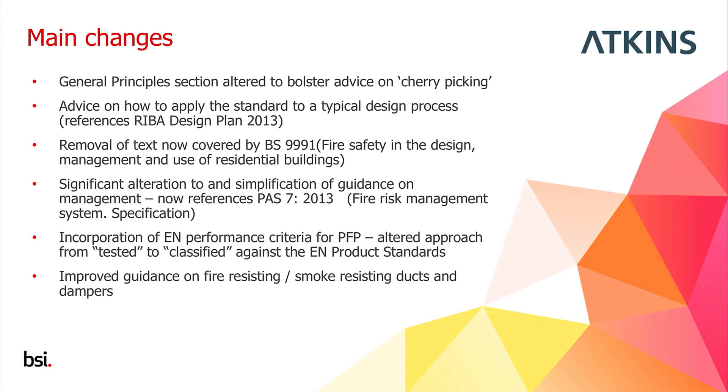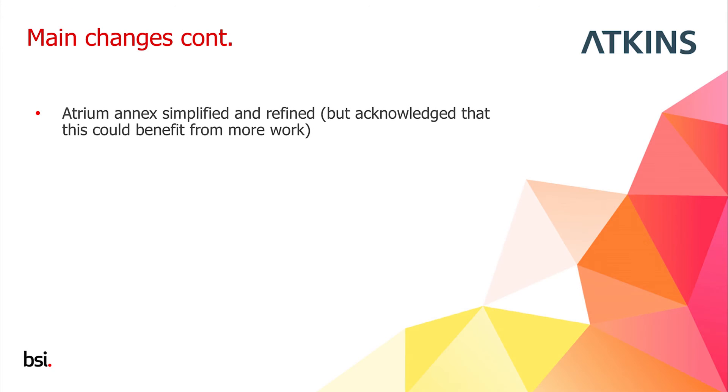Improved guidance has been provided on fire-resisting and smoke-resisting ducts and dampers, an area where mechanical engineering colleagues often get confused. The clarification addresses how to specify fire-resisting ducts and dampers, where to place them, and whether a fire-resisting damper, a smoke-resisting damper, or a combined fire-and-smoke-resisting damper is needed to maintain compartment lines.